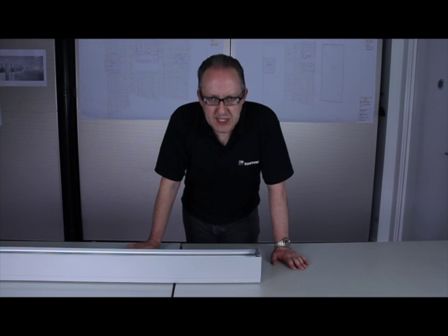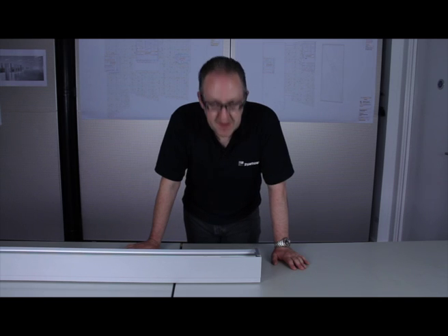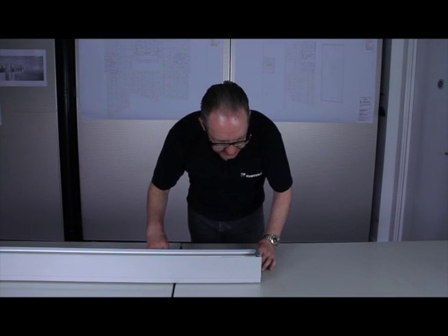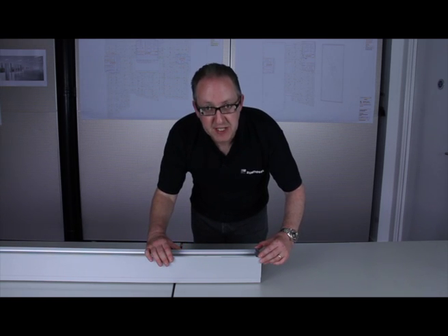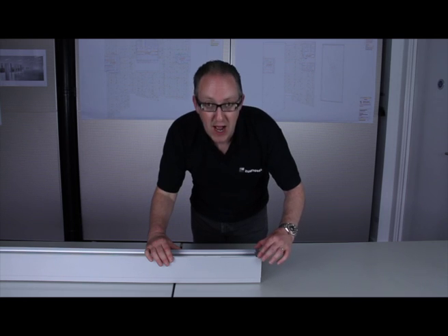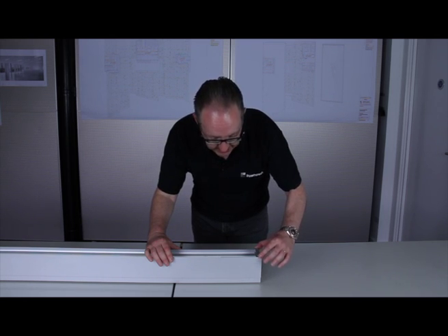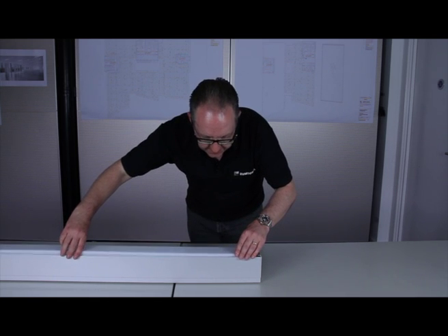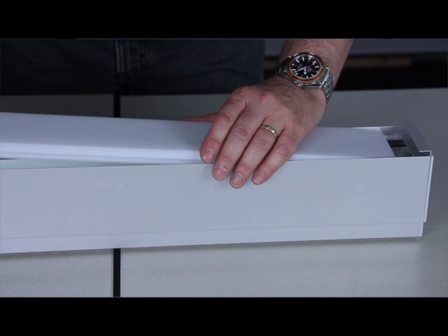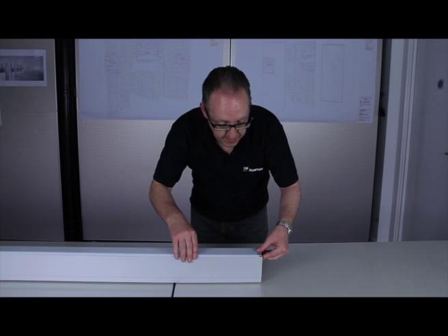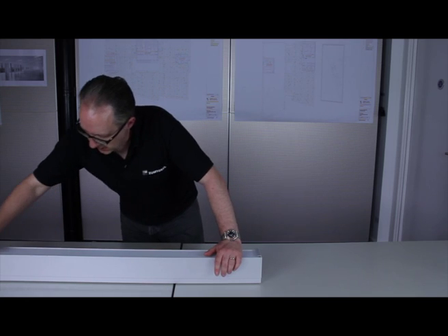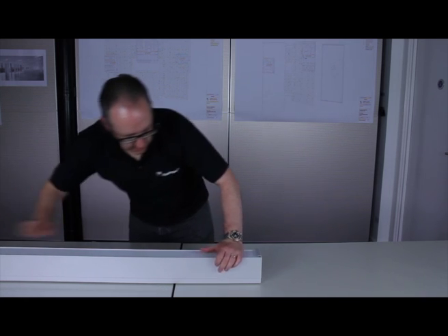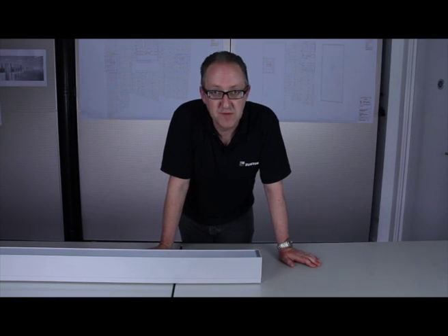The last thing to do before completing the ribbon of slot light is to fit the diffuser. This is a simple thing to do. Insert the diffuser fixing bracket that was supplied with the end caps about halfway into its clips on the end cap, and then offer the diffuser up to the slot light system. Slide it along above the bracket and then begin to clip the diffuser in all the way along, and finally press the bracket until it's flush.